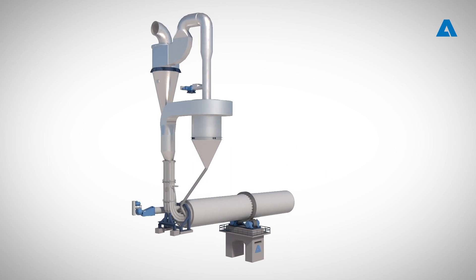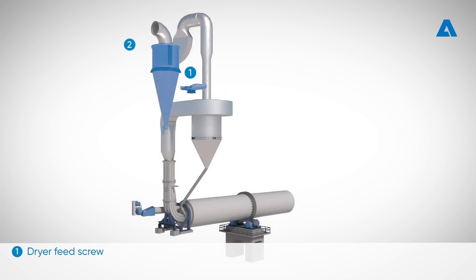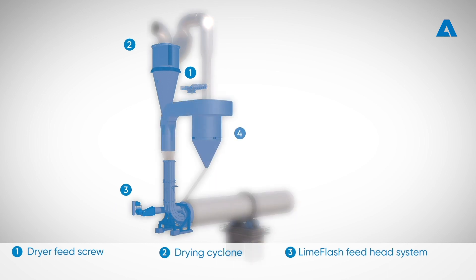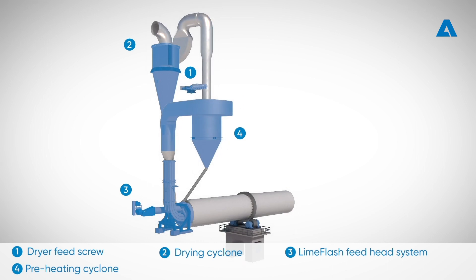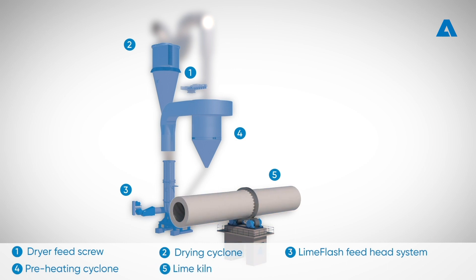Andritz' two-cyclone LimeFlash H system contains the following main components. Drier feed screw enables lime mud entering into the LimeFlash H system. The first cyclone, called the drying cyclone, separates the dried lime mud from the flue gas. The LimeFlash feed head system allows the process to operate at a higher feed and temperature without plugging. The preheating cyclone is the second cyclone, which represents a new feature of the LimeFlash H system, where lime mud is further heated up. Lime mud flows by gravity through the preheating cyclone through a chute to the rotating lime kiln.